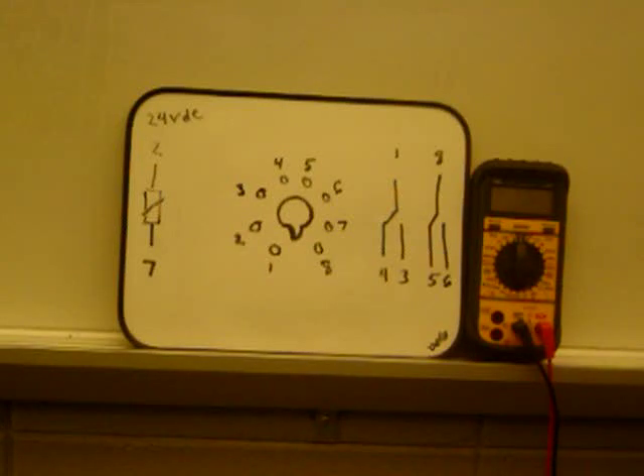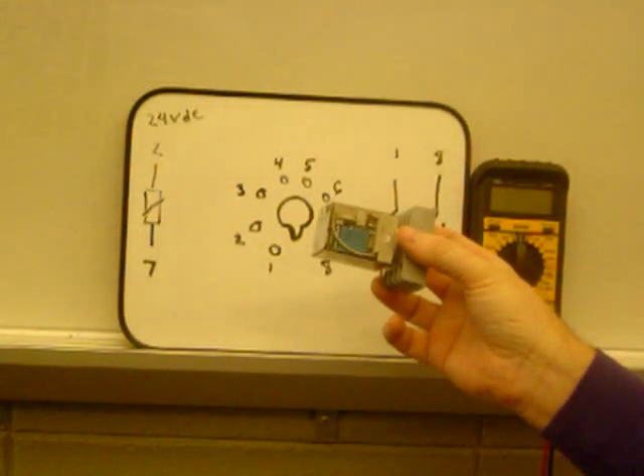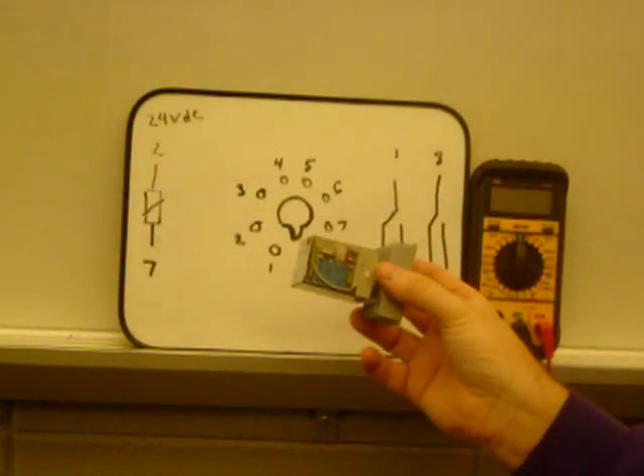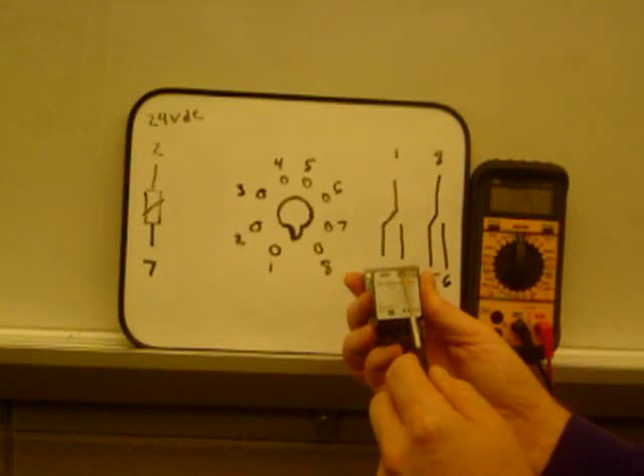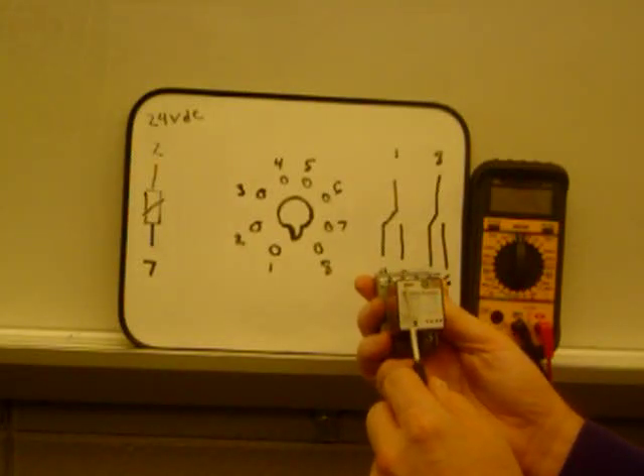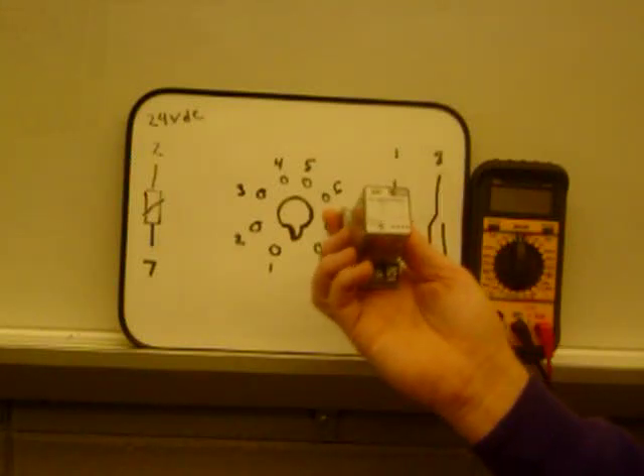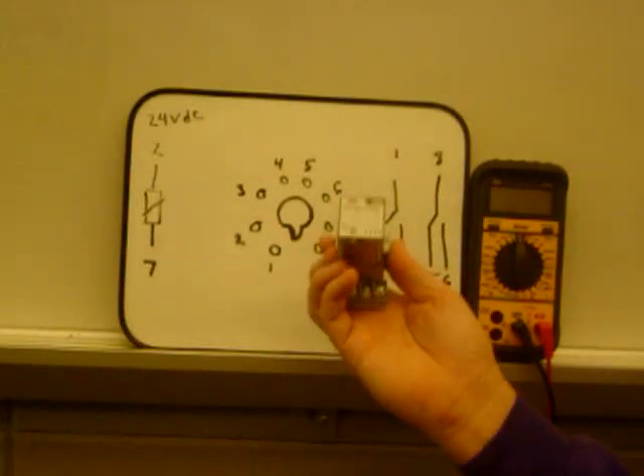One of the things that you want to do when you have to check a relay is, first of all, most relays you can have a visual indicator of whether or not it's moved. You can look through the glass. You can see if the little contact here is moved from one position to another. This one has a light that would come on telling me that it's energized. Sometimes I have a little window here with an indicator, but being in maintenance, eventually relays fail. How do I check them?